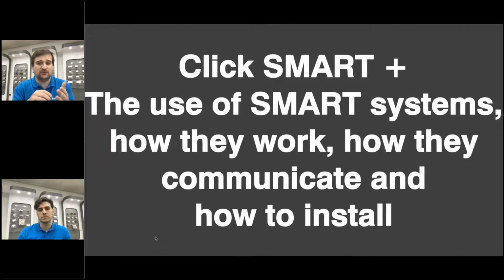Now, typically what you find when you're looking at automation, which is where we are with the smart installations, is a bandwidth of 868 megahertz, I believe, Jake. Yep. So that means my receiver is going to transmit that signal, and then I'm going to receive it, and nothing else should affect it. So now if I put something a long way away, and we're talking typically, the furthest you can go is what, 100 meters, Jake? 100 meters, but that has to be clear sight all the way through. So there can't be any interruptions.